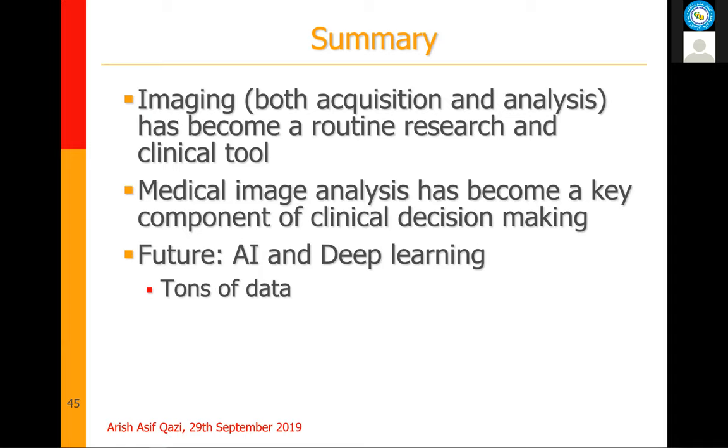Another problem is regulatory limitations. Any algorithm that you develop actually needs approval. You can't just develop a method and release it. It needs to be accepted by FDA or European authorities. Now, FDA has been very conservative about approving deep learning systems. And even if they do, they accept the systems to be in a locked state, which means that those systems cannot adapt themselves to new data. And if they have to retrain their methods on new data, they have to apply for another approval.